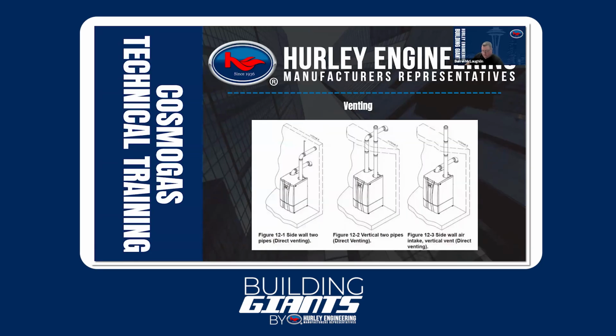Venting options. So again, these are already commonly vented with multiple heat exchangers inside the cabinet. We can do sidewall venting. We can do vertical terminations. We can even do sidewall intake and vertical exhaust. What we would like to avoid is having opposite sides of the room, so having our intake on the east wall and our exhaust on a west wall. Pressure differences, winds, alcoves, all those things could cause problems with these burners and with any low NOx premix burners.